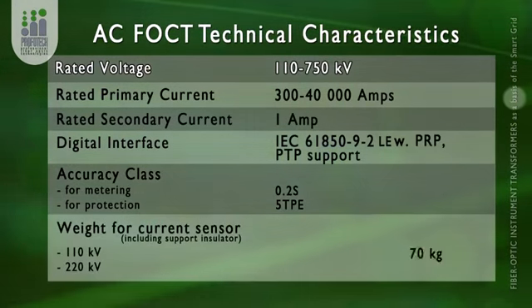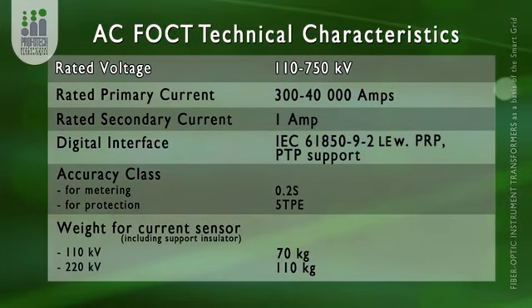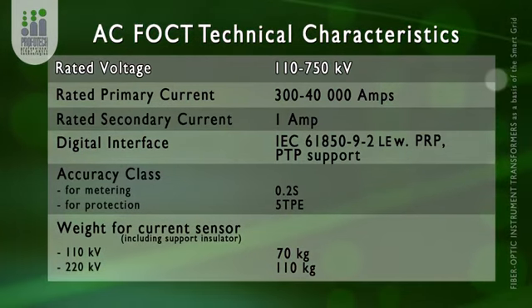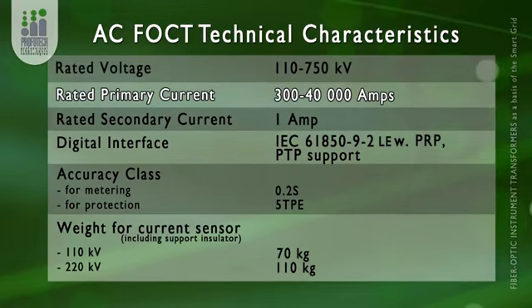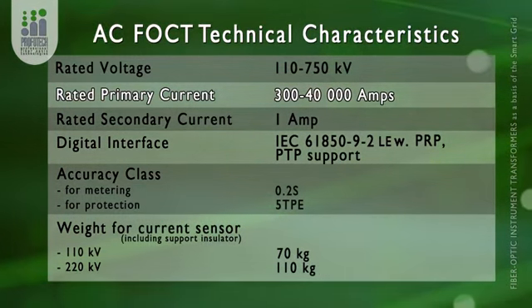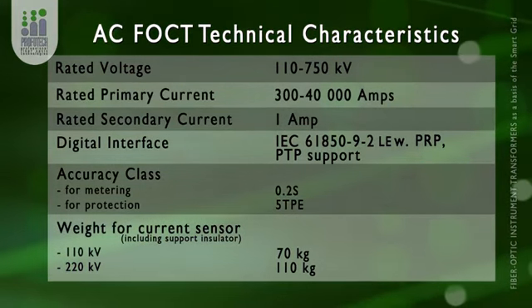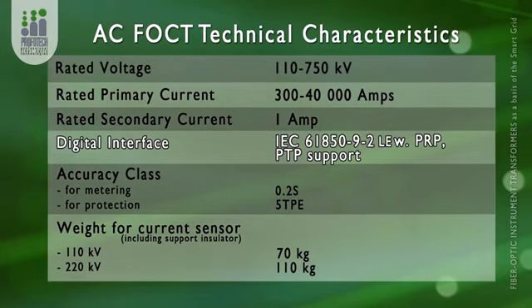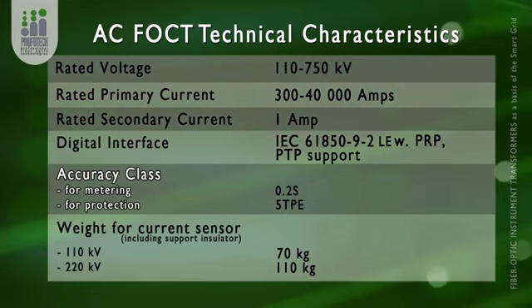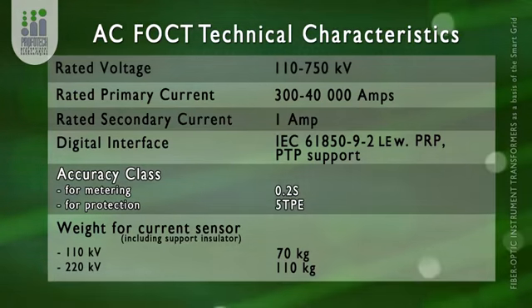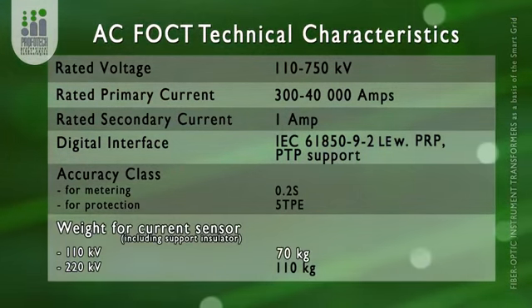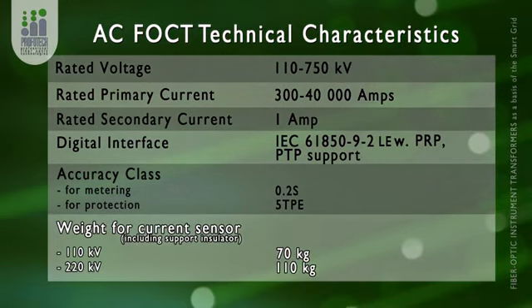I would like to say something about the characteristics of this sensor. It can be used at any voltage you like because it's absolutely insulated from the primary voltage. So it is independent of the voltage in the line. Second, we have a very large and very broad rated primary current, and it can be from 300 to 40,000 amps rated current. The interface is fully digital according to the IEC 61850-9-2 protocol. Its accuracy class is 0.2S for metering and 5P for protection. And the weight is 70 kilos for 110 kilovolts and 110 kilos for 220 kilovolts. Its weight depends only on the weight of the support insulator, not the sensor itself.